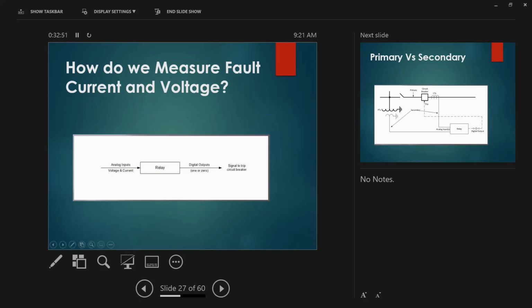My mentor said there is no real time in terms of measurement. Even though electricity travels at the speed of light, you still have some kind of delay. If there is a fault, I can remember this 20 years ago, the signal is sent to the relay and the algorithm will process it. With the speed of the computer or memory inside the relay, it will determine whether this is an instantaneous trip or an overcurrent trip. That process inside the relay creates, let's say, milliseconds of delay before you can initiate the outcome, like trip or no trip. And the breaker as well has its own delay. That's why you're measuring the opening time and closing time. So that's how it works. There's some kind of process or delay before you can see the outcome of that specific fault in the system.